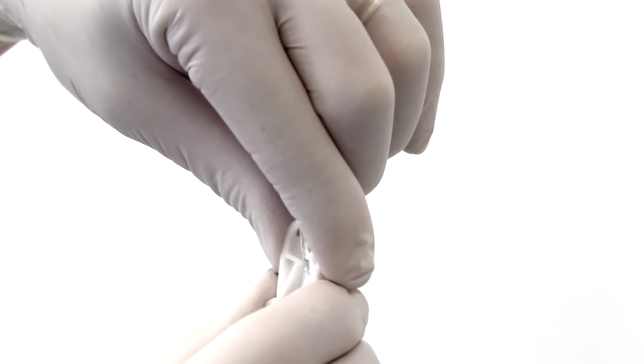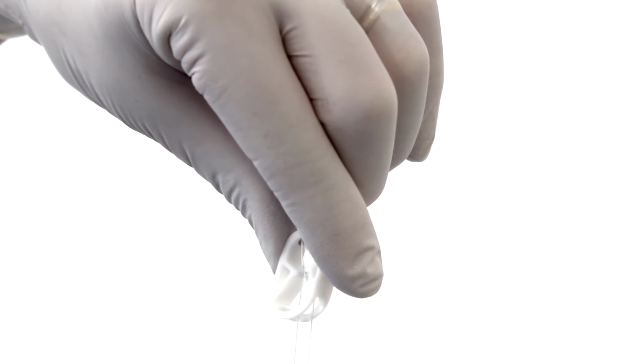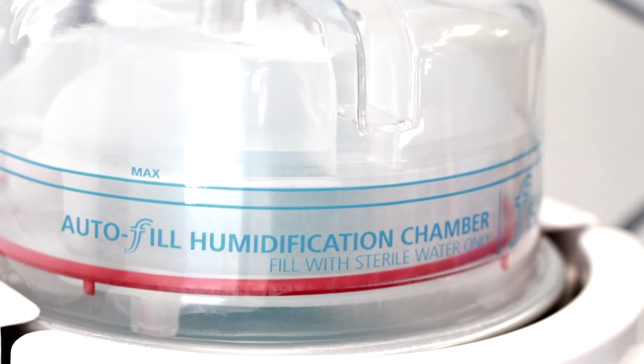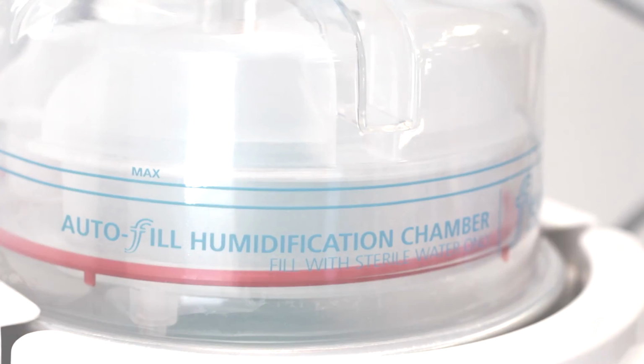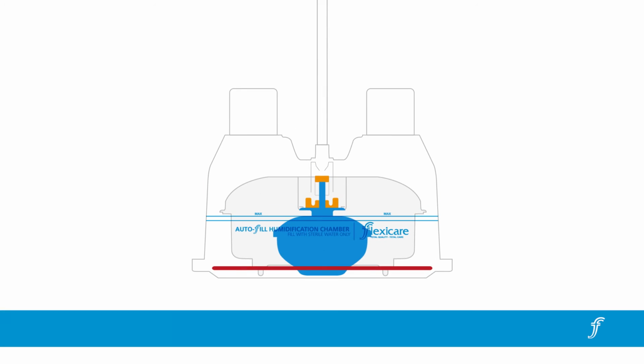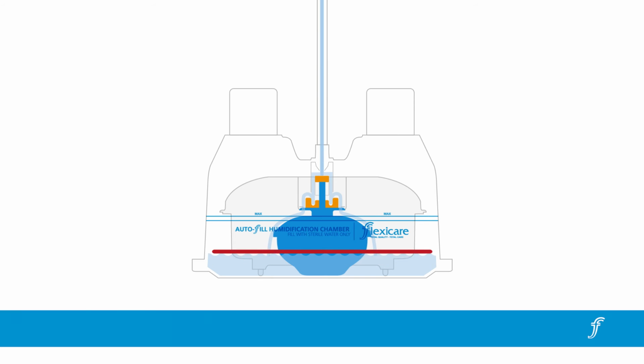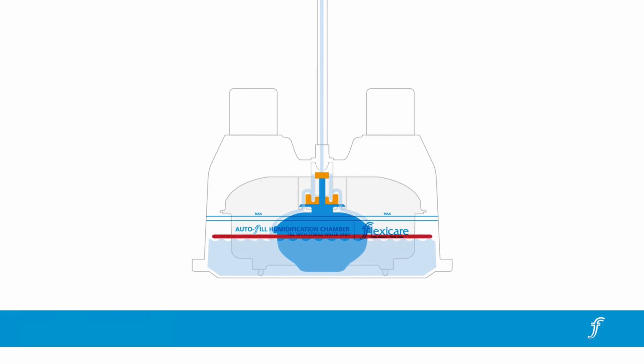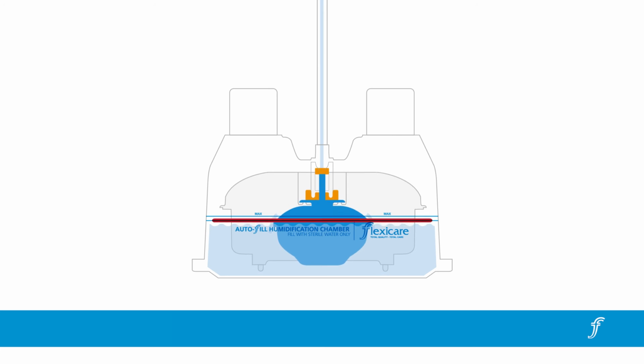Once functional testing is completed, open the pinch clamp and allow the sterile water to flow into the humidification chamber. The Flexicare autofill chamber also has a unique secondary valve system, which acts as a safety feature to prevent overfilling of the chamber should the primary valve fail. The secondary valve will shut off the water flow when the level reaches the maximum as marked with a double line on the side of the chamber.